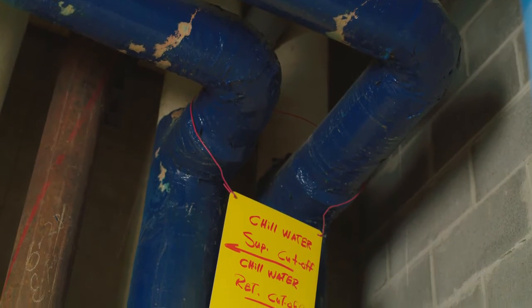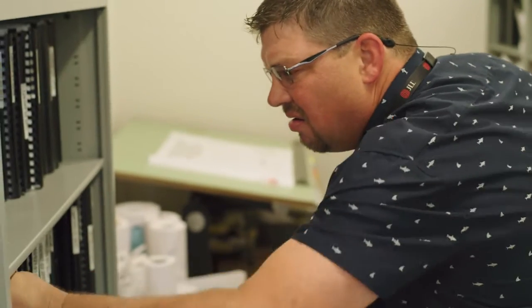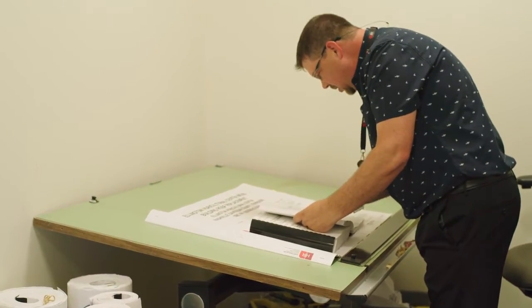Basically, we were pushing water too fast through the building. We didn't have time to completely get a good thermal transfer. Initially, we saw anywhere from a four to eight degree delta T. The contracted number for that site is 14 and a half degrees, meaning anything we sent back below that 14.5-degree contracted number, we were paying a thermal inefficiency charge. In some months prior to us taking over the contract, those charges exceeded $12,000 to $13,000 in a single month for that building.